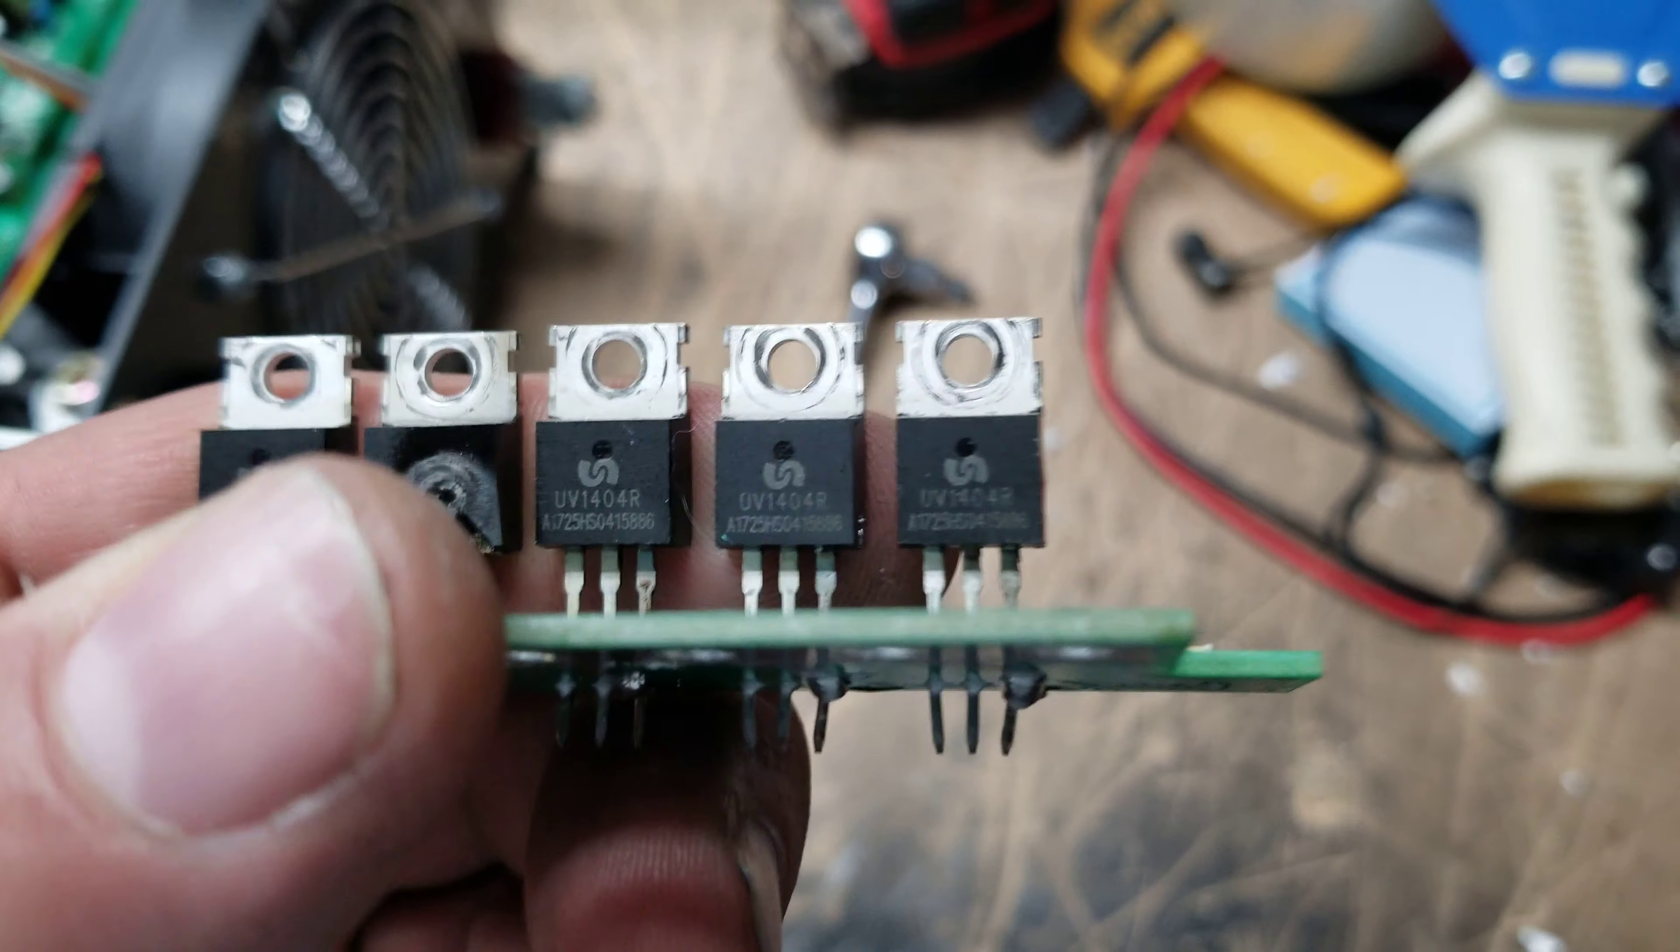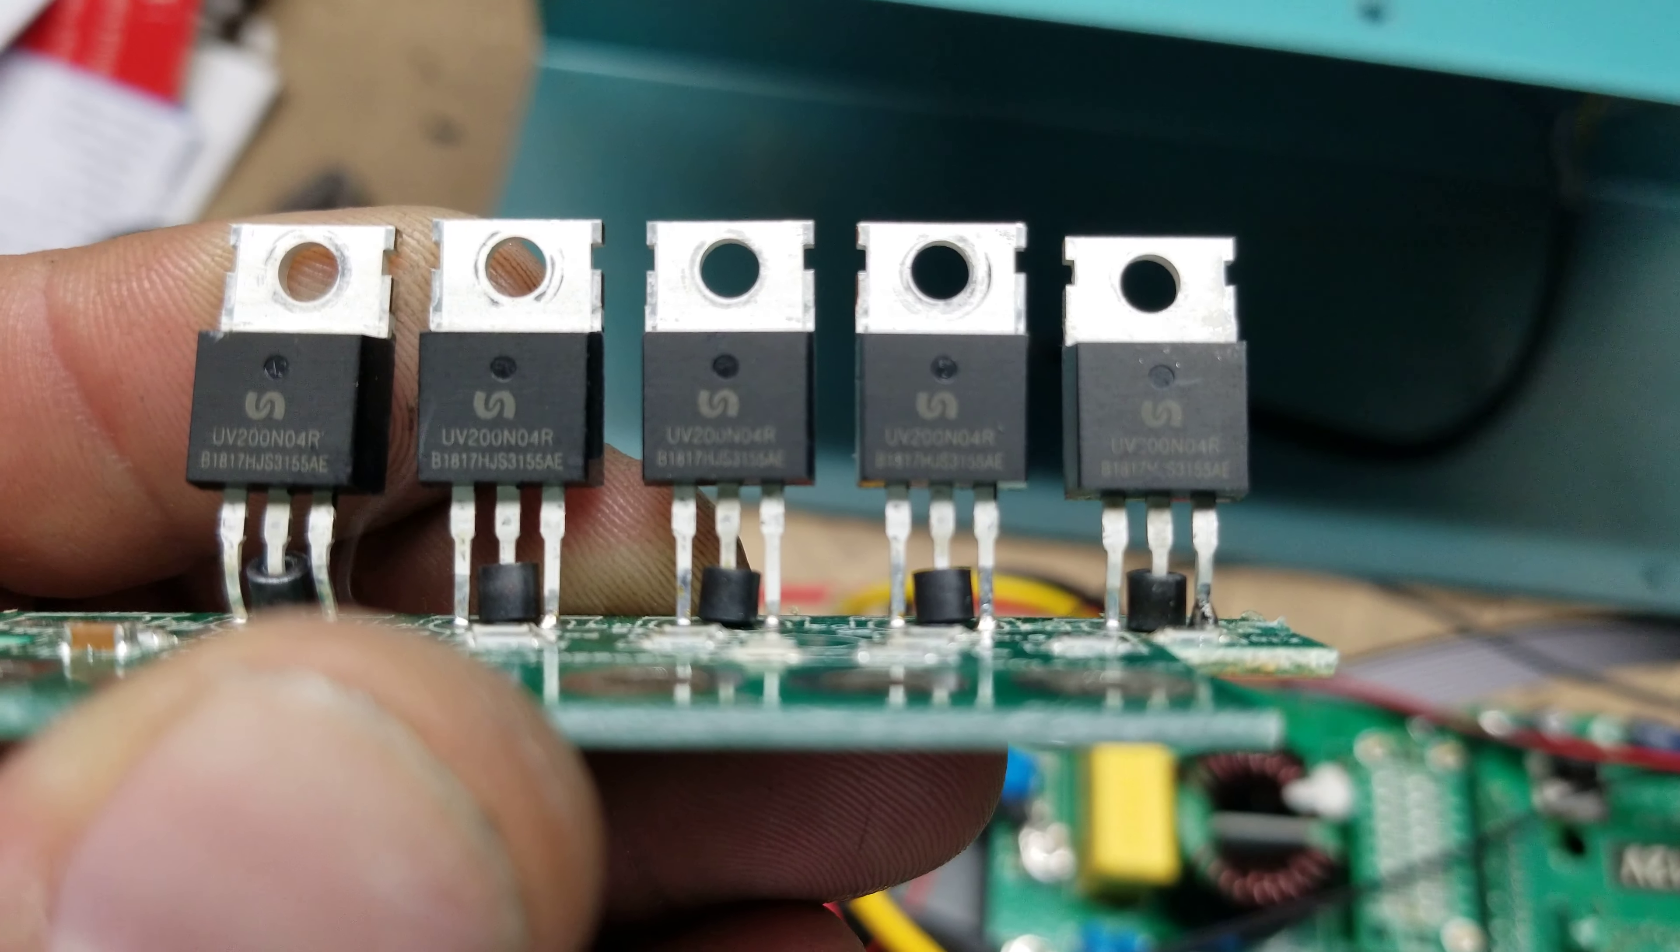These are different, but these here are the old ones. So these are 1404Rs, they were replaced about a year ago with these 200N04Rs. Now, what you'll notice, there's still a charge on those over here, but on this side here, this is the AC side, you can see that these are not lit up.